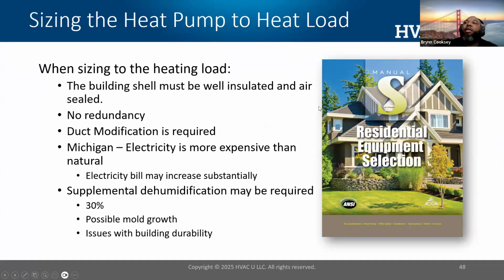When sizing the heat pump to the heating load, follow Manual S guidance. The building shell should be well insulated and air sealed. And with this option, you have to remind customers that there's no redundancy. And oftentimes, because heat pumps require more airflow, you're going to have to do a duct modification.